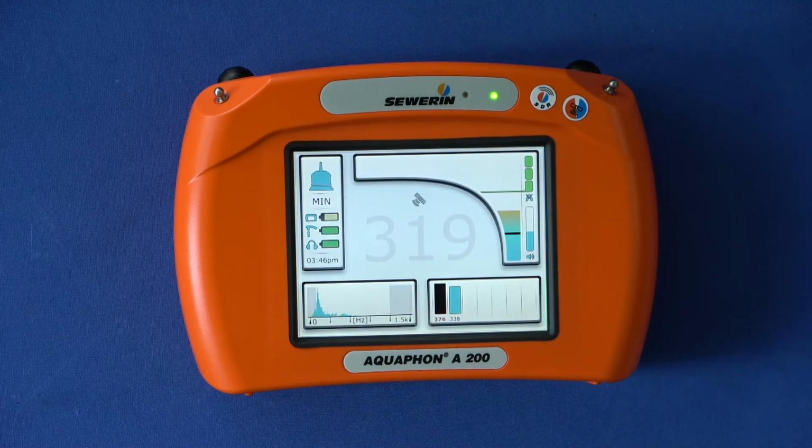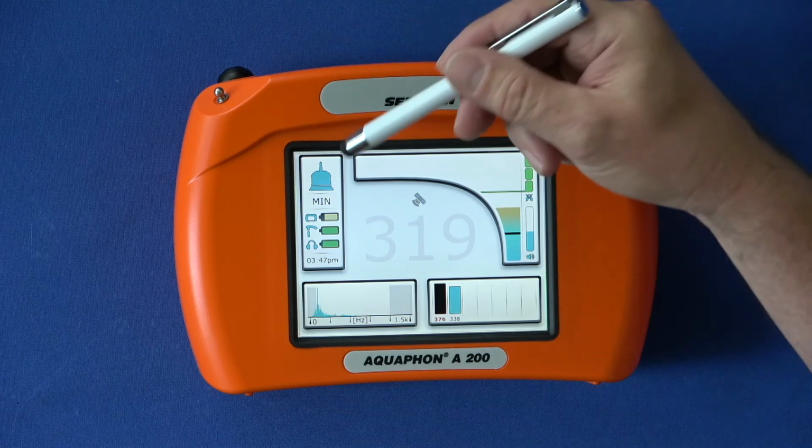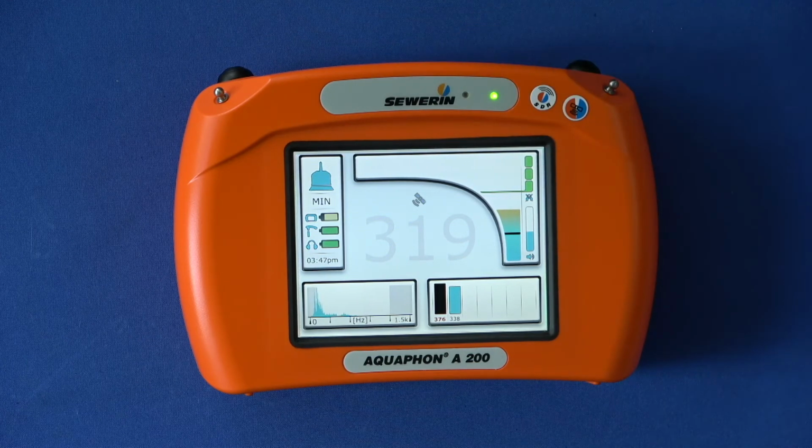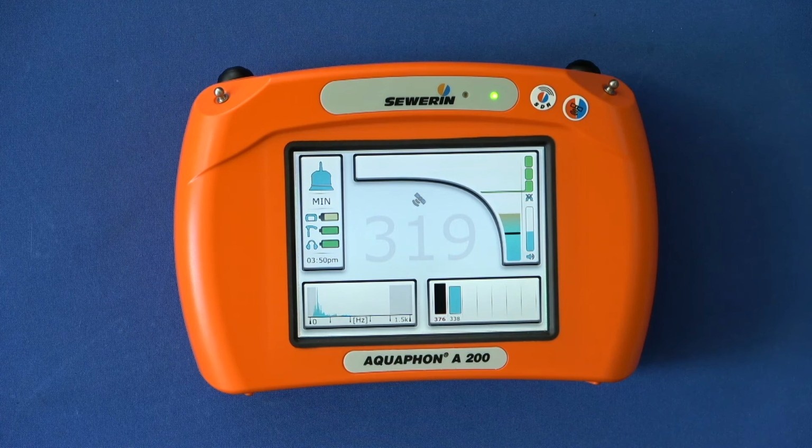You will return to the measuring mode and you will now see an icon for the connected microphone instead of the application in the top left corner of the Settings button. If you switch off the A200 after completion of the location, the filter settings for the microphone in question are saved and are then available again exactly the same the next time you start the device.